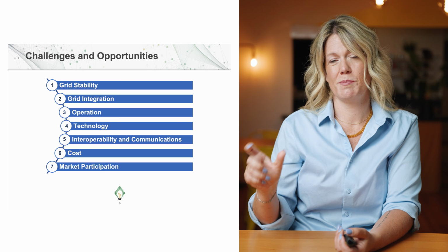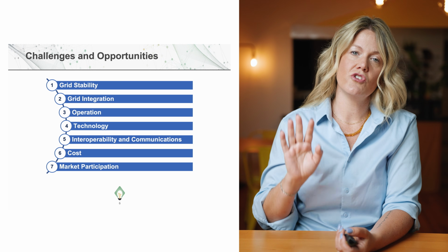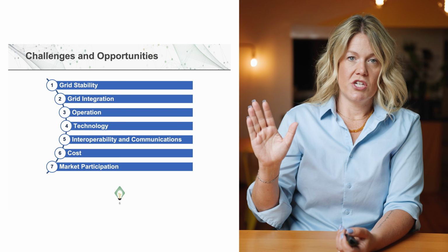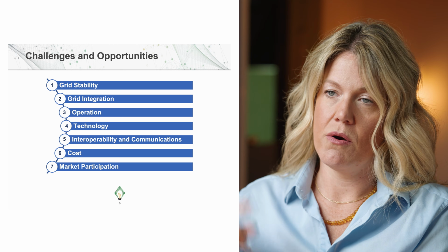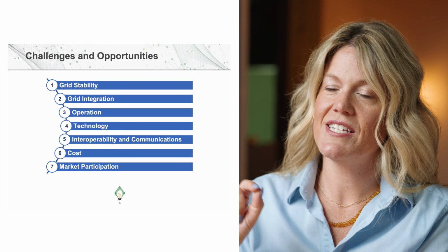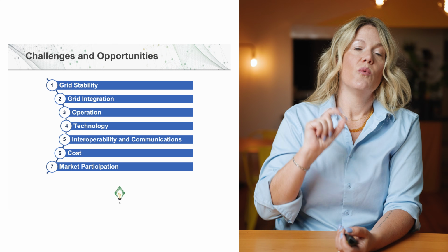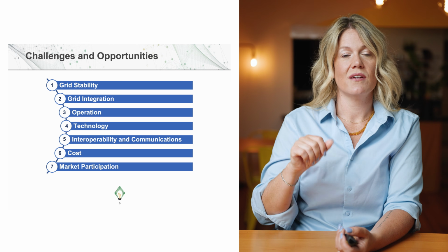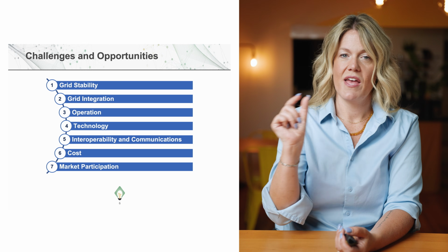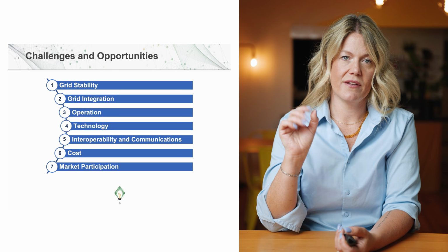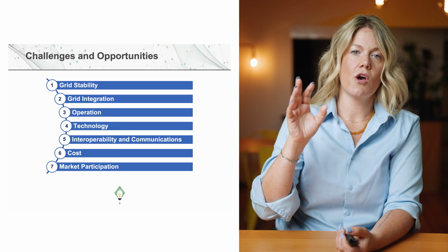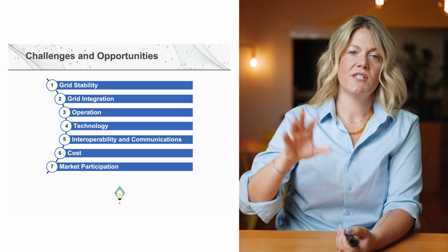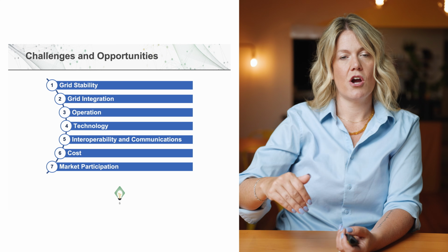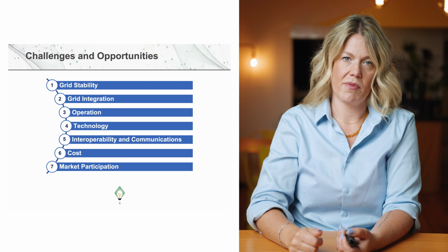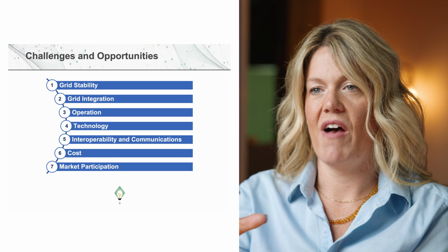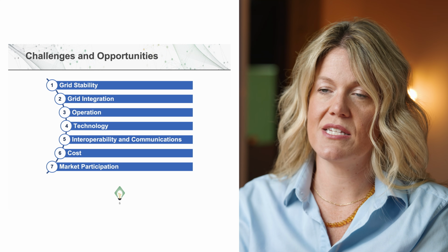So, grid stability — that's probably number one, especially on the transmission grid. Our transmission grid maintains power 24/7, 365 under 60 hertz frequency here in the States, meaning massive machines spinning at 60 hertz constantly, with very limited room for error, less than 0.5% hertz. If something goes off kilter — a major disruption or system fault — and those large systems can't maintain stability, you can have cascading blackouts. So if we have a large enough set of IBRs not coordinated with the grid to maintain that stability, there's a concern.